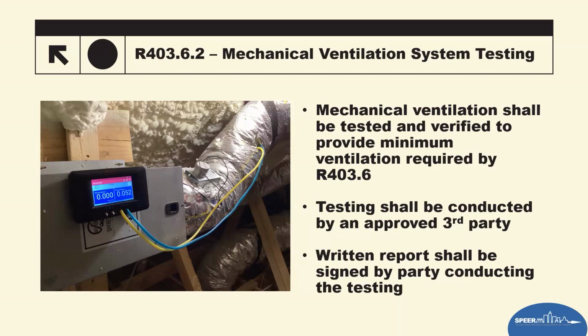The testing must be conducted by a third party, and there must be a written and signed report of the testing results that is turned in to the building official, or AHJ, to show that it's compliant. The code is kind of lenient on what equipment to use. It shows you how to do the procedure as far as what's allowed, but it doesn't say use this specific equipment. So if I use what we see in the picture and an HVAC company uses a different manometer or testing unit, we're going to have different results. So you kind of just have to lean on the third party to do the right thing. If they say it is failing, then more than likely they have more accurate equipment that says it's failing. Those manometers you see there are $1,500 and are highly accurate as long as they're calibrated on the manufacturer's schedule.